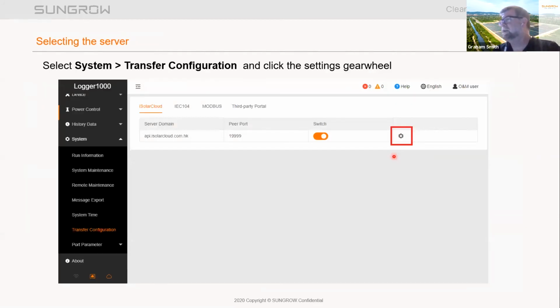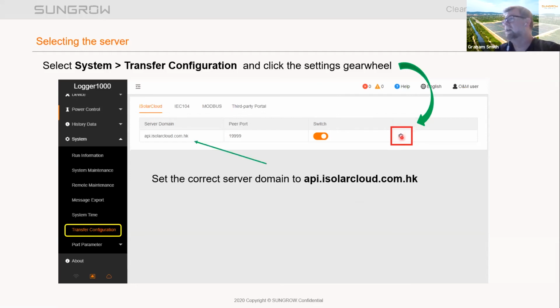Next thing you want to do is the transfer configuration. If you go into system transfer configuration here, there's just a little adjustment you do need to make, because this is a global supply and you need to set it for our region. Hit this little gear wheel here, which is the settings, and you have to make sure that is set to api.isolarcloud.com.hk. In the default, it doesn't have the .hk, and if you don't set that, once again, it will go up to another server and you won't be able to view it here. So just make sure that that is set to HK and save.